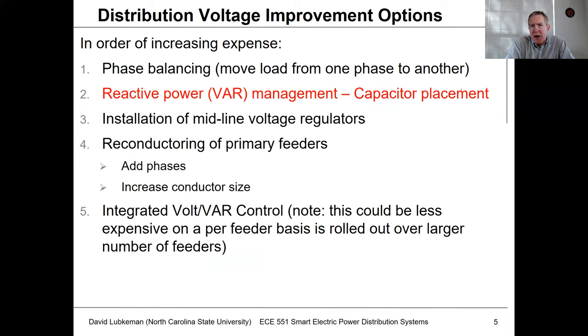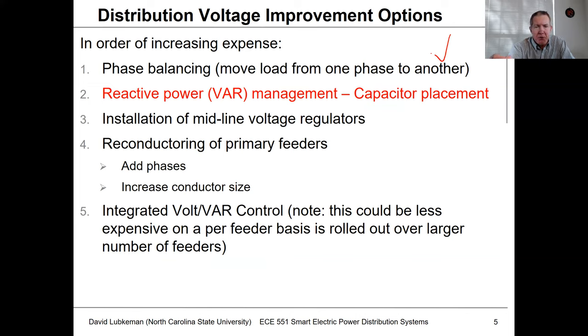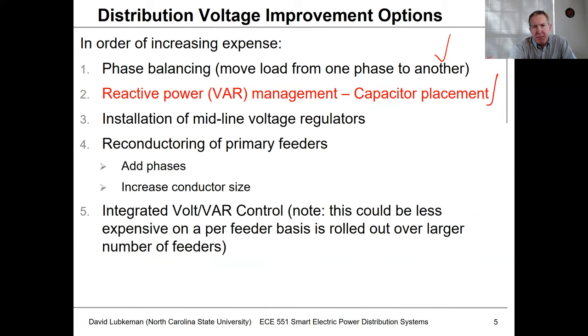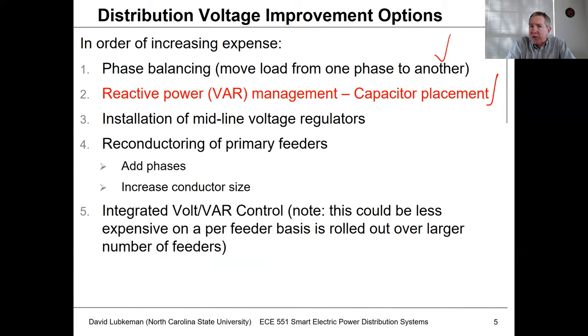Capacitors can be a very effective tool for improving voltage. As far as things we'd want to do on a circuit in increasing order of expense, the cheapest is balancing the circuit — reducing neutral and earth return current, which makes the circuit more efficient in terms of voltage drop. The next option is capacitor placement, which compensates for reactive load mostly due to motors, supplying reactive current locally through a capacitor rather than drawing it all the way from the substation.